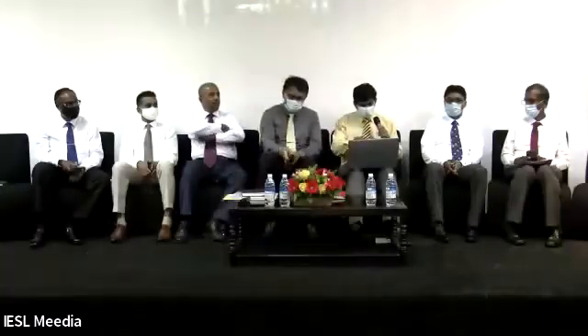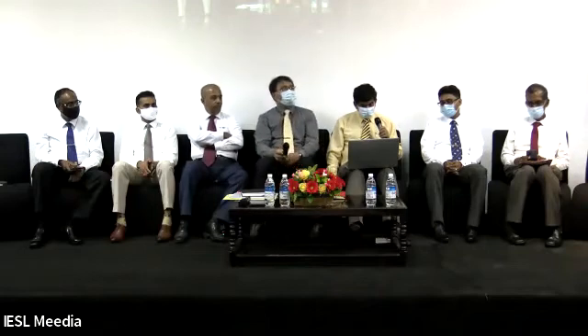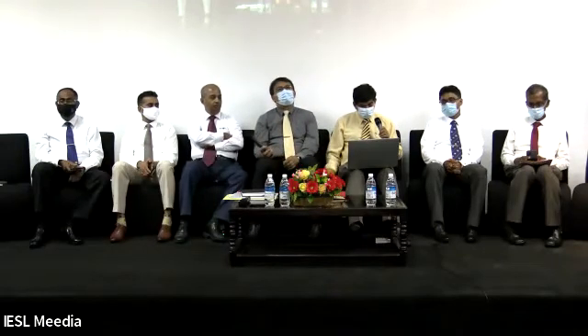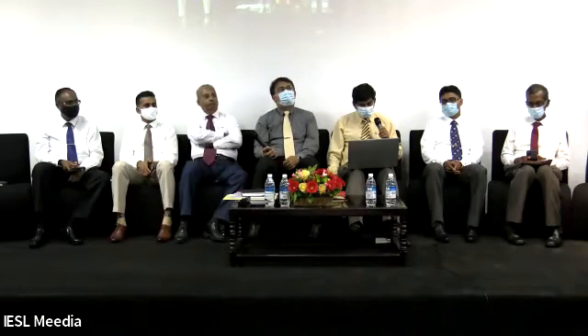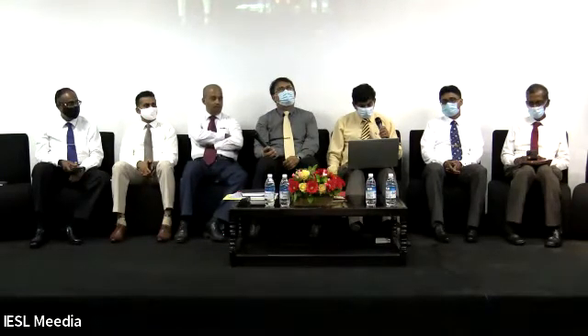The same question was here from somebody called Jagat. The blackout happened due to 3 main reasons: the incorrect earth fault settings, the incorrect earth fault protection wiring, and the November 29 trip incident, to which less attention was paid. Why should CEB not have taken care of those in the early stages, as it eventually cost millions of rupees lost to the Sri Lankan economy? Any response?